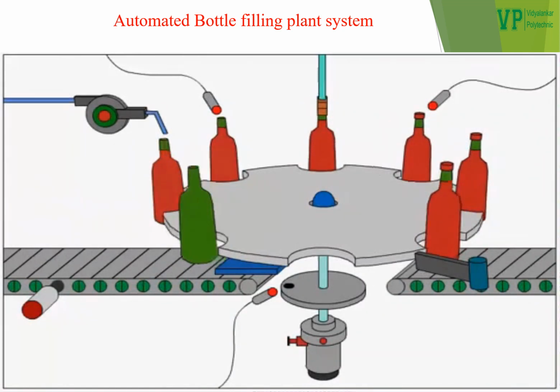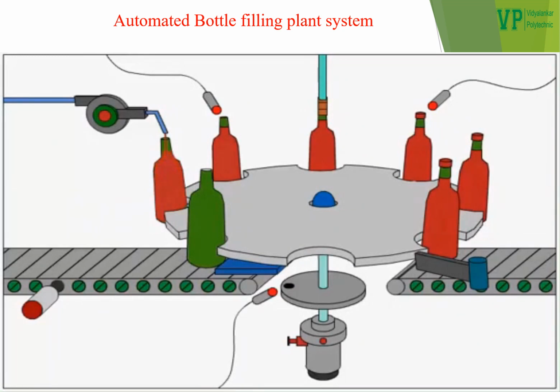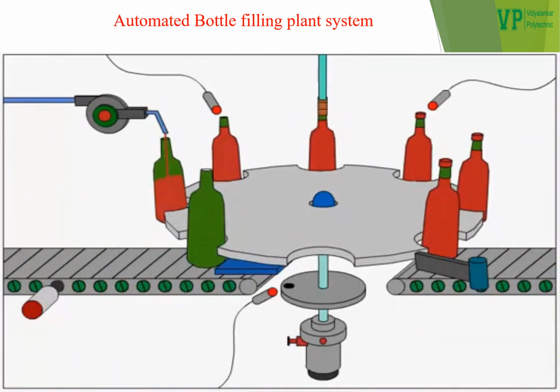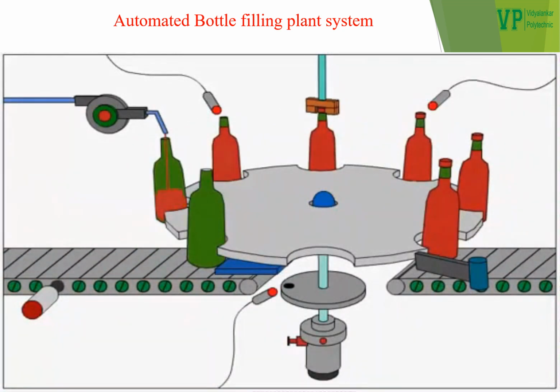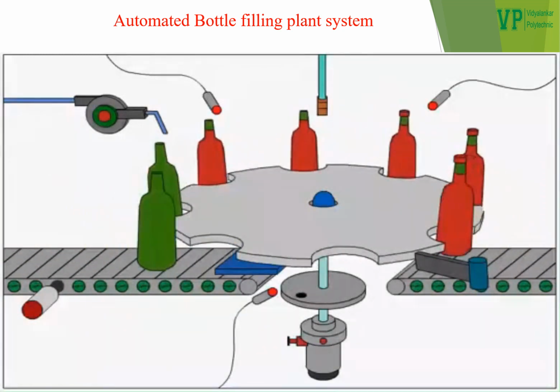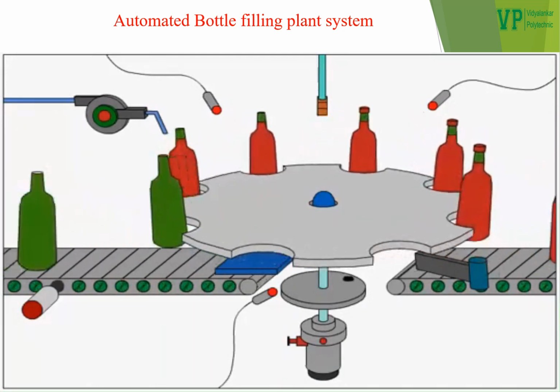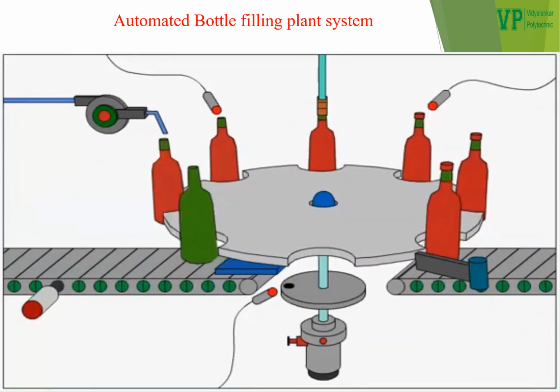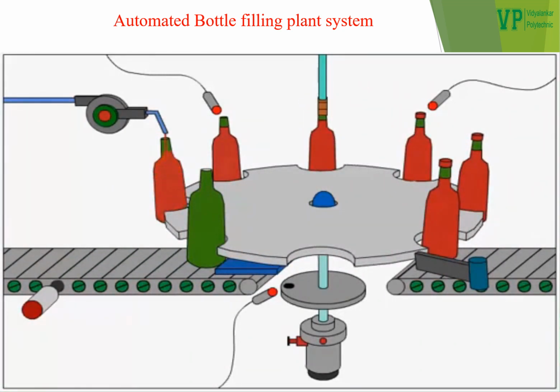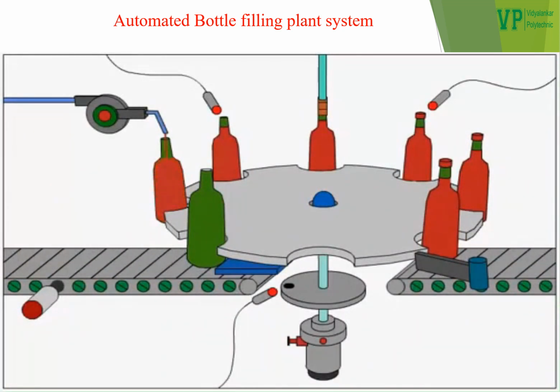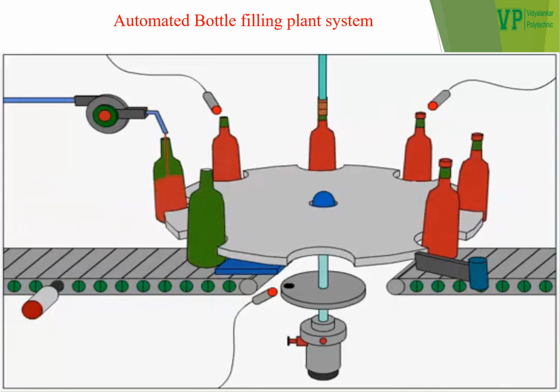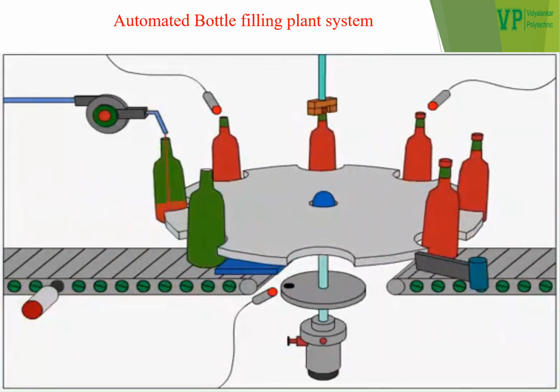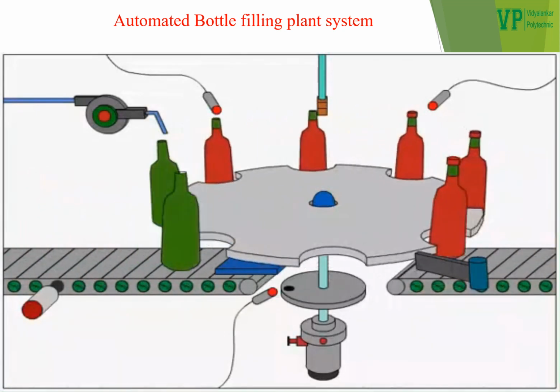Other than that, we can also notice a liquid dispensing unit and a bottle capping unit. Both these units are connected to another two outputs of the PLC. So in all, we see that there are 4 outputs connected to the 4 output terminals of the PLC. Other than that, we also have the input sensors connected to the input module of the PLC. One of the sensors is connected very close to the rotating shaft. The other 2 sensors, which detect the presence of a bottle on the rotating disc, are placed on either side of the bottle capping unit.